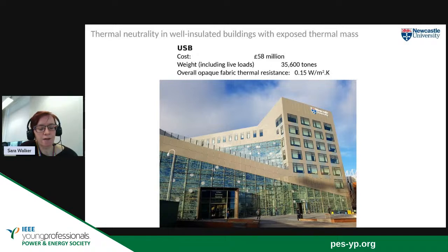This building cost 58 million to build. Some of that is the extra sensors and so on. But in terms of the building itself, it is what we would call thermally heavy. It's quite slow to respond to external temperatures, which is great because potentially this enables us to use the slow thermal response of the building as essentially a storage mechanism to enable us to defer our heating or cooling electrical load for periods of time and help the local network.